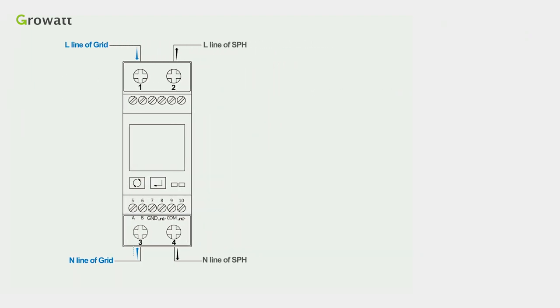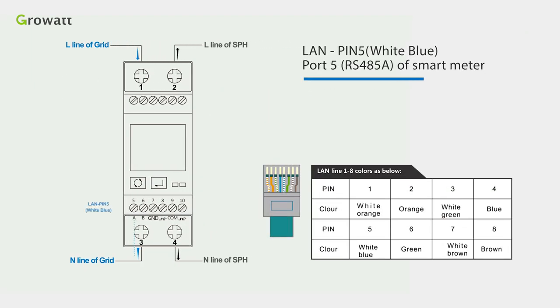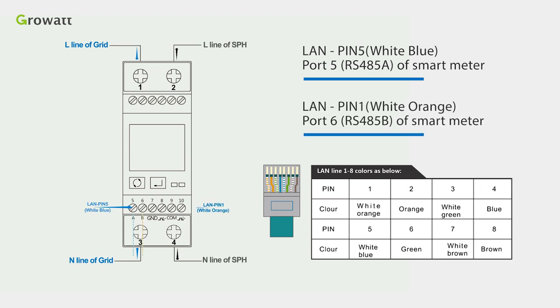Secondly, connect the PIN 5, white-blue, to port 5, RS-485A of the smart meter, and LAN pin 1, white-orange, to port 6, RS-485B of the smart meter.